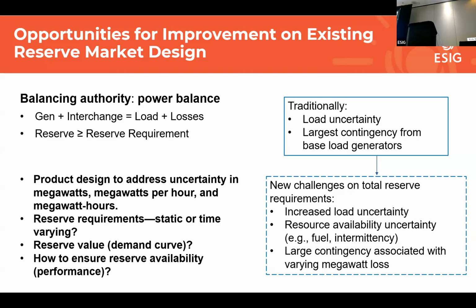So how do we predict this kind of event and set up the reserve requirement more dynamically? Because if you always cover the worst case, it could be 5,000 to 6,000 megawatts. It's going to be very expensive to the market. If you can be smart enough to say some hours I only need 2,000, some hours maybe 6,000, that can bring a lot of efficiency.